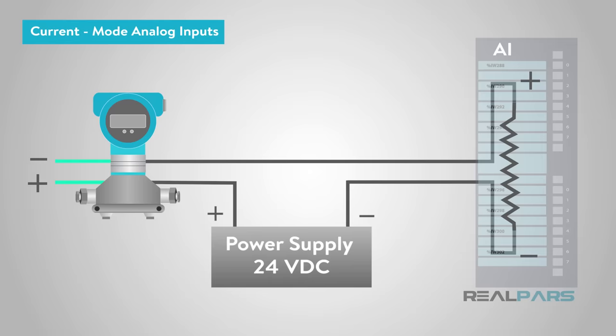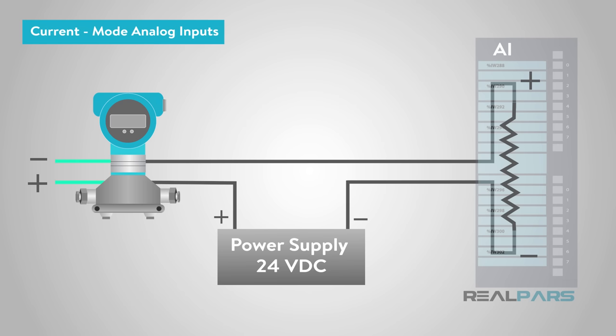Note that the positive and negative measuring device connections are different from the previous example. The current comes from the power supply in the positive terminal of the loop-powered device, and out the negative terminal and into the positive PLC terminal. What we have covered so far have been generalized inputs, used where the field signal is set up as a conditioned input for the PLC.